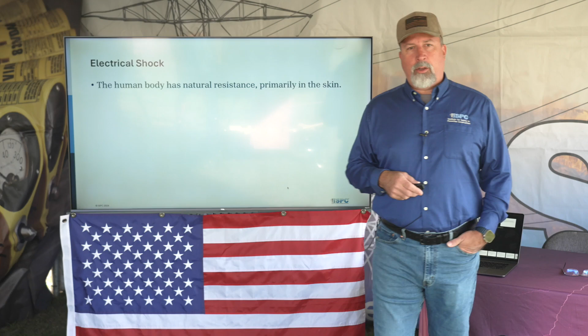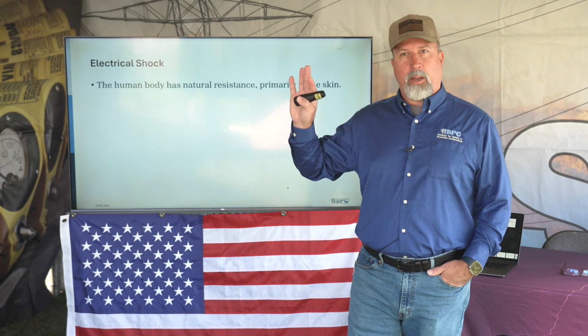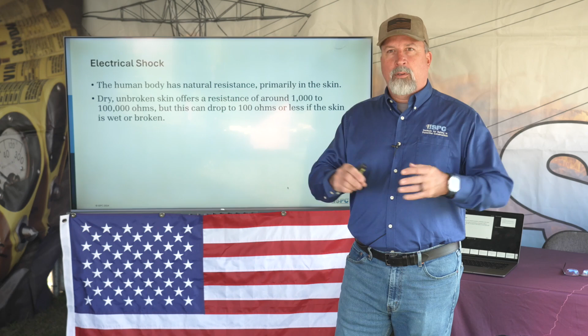As we said earlier, the human body has natural resistance to electricity, primarily in our skin. Most calculations our industry and OSHA use are based on a resistance value of 1,000 ohms. Depending on your body makeup, resistance can be anywhere up to 100,000 ohms. But when you bring in moisture, sweat, or open cuts on your hands, that resistance could drop down to as little as 100 ohms, making you much more susceptible to electrical shock.